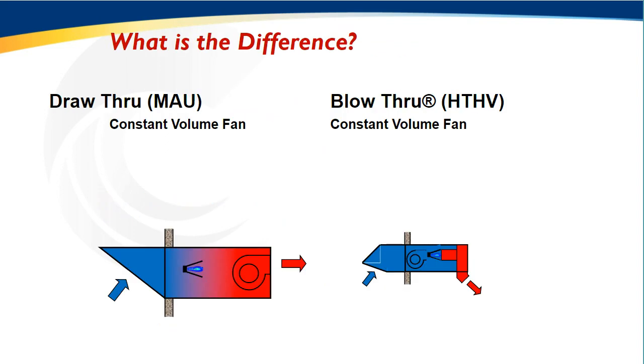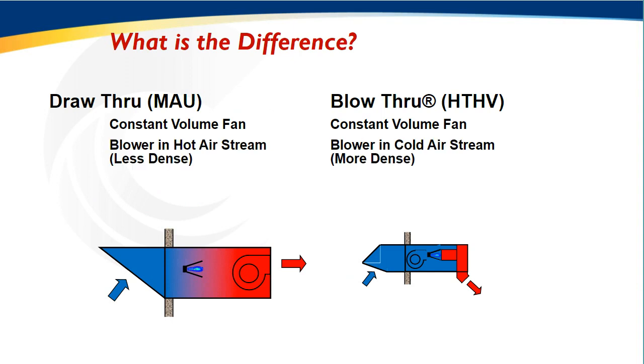So let's look at what happens if I try to utilize a standard draw-through makeup air system and deploy it against a standard HTHV system. How is that going to impact my ability to heat a space? Well, both systems typically have a constant volume fan. The blower in the makeup air system is in the hot air stream, such that it's processing less dense air. Density is not a concept that we talk about that much in our industry, but we'll go into more detail later.